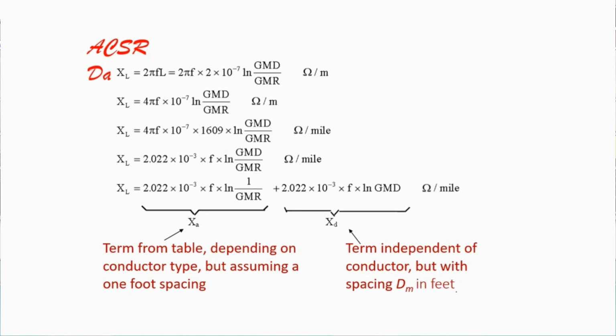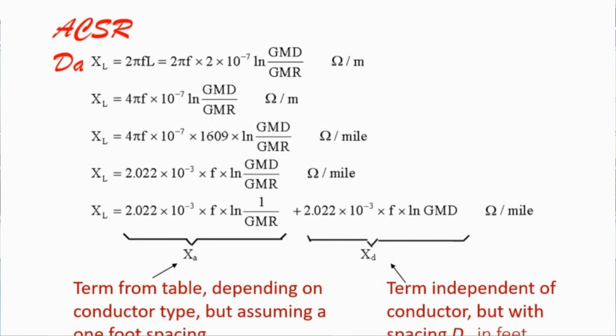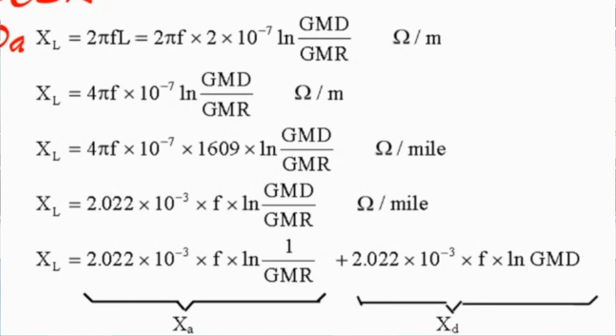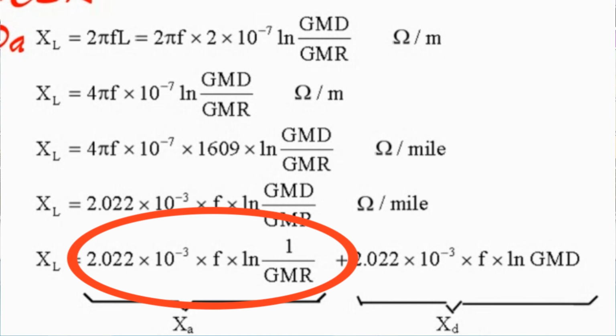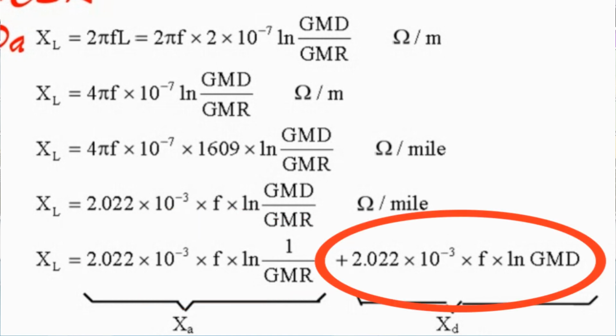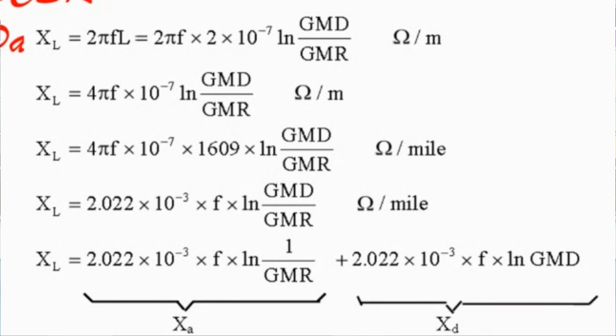This equation - take the constant outside, they split it into 2 parts. First part will be 1 over GMR, the other is GMD. You know from mathematics, this is ln A plus ln B - you can split it this way. They split it to show that in the manufacturer data sheet, the first part depends on the conductor type, while the other one, GMD, is the distance - it doesn't depend on the conductor type, regardless of the conductor. It depends on the space between the conductors. That's why it was split. The first part gives XA, the second part gives XD.